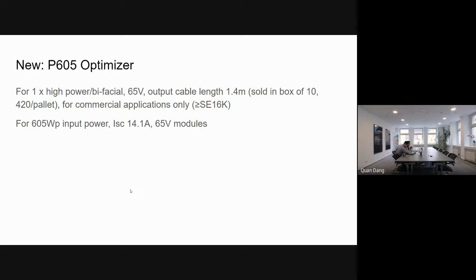It's not normal, because usually the optimizer can be used with one module only with residential; this one is an exception, so be careful with that. They introduced this mostly because sometimes you have a string where you don't have enough - if you use the dual optimizer you cannot have enough minimum optimizers, so in this case they use it. It's a little cheaper than the dual optimizer and can work with bigger modules. Of course, the installer or designer needs to use the SolarEdge Designer tool, which will recommend it automatically. However, this is a new thing for you.